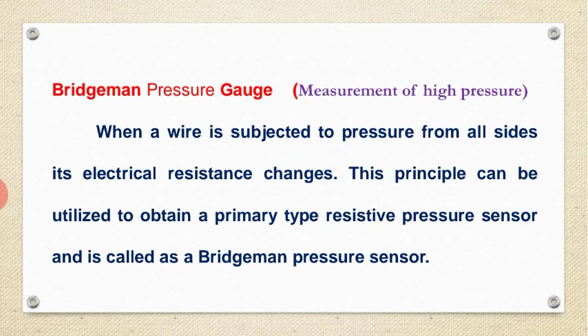This is the figure which gives a Bridgman gauge, how it is implemented. Here they put the sensing element. The pressure connection is connected here, and this is the terminal where the resistance element leads are taken out. The sensing element does not actually contact the process medium but is separated from it by a kerosene filled bellows. So here kerosene oil is filled, and there is a bellows.